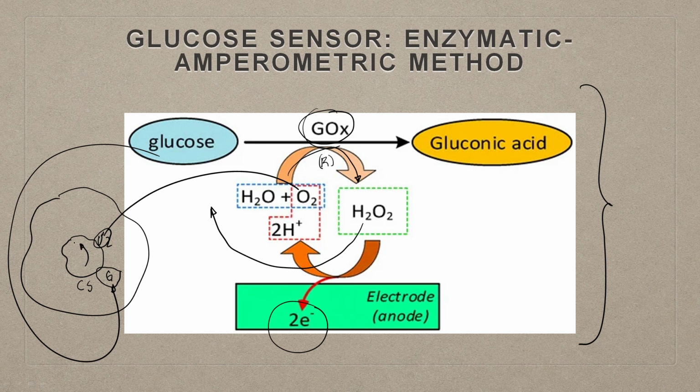So, one of the challenges we discussed in the last class, if we look at it in space, especially in a 3-dimensional space, if the reaction is taking place so deep inside the pocket, for an electrode sitting somewhere out here, there is a lot of loss of signal by the time it reaches here. So, you need a substantial amount of glucose to get converted. If your sample has less glucose, the sensitivity will be compromised. In order to circumvent that problem, a lot of development has happened.